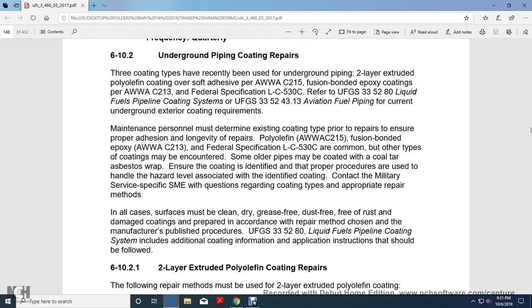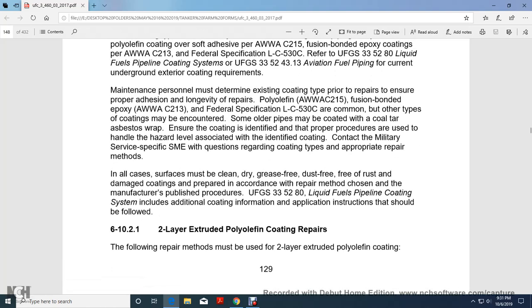Alright, your underground piping coatings and repairs. 3 coating types that have recently been used with underground pipe: 2 layer extruded polyolefin coating over soft adhesive, AWWA C215; fusion bonded epoxy coatings, AWWA C213, federal specification LC530C, with Unified Guidelines Spec 335280, liquid fuel pipeline coating system. Unified Guidelines Spec 3352-4315, aviation fuel pipeline, is current for the underground exterior coating requirements.